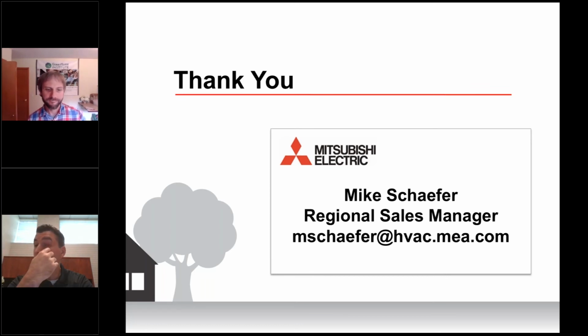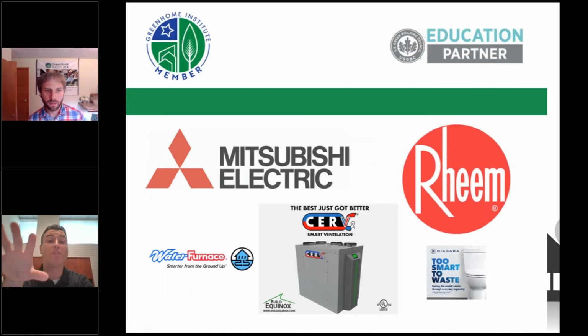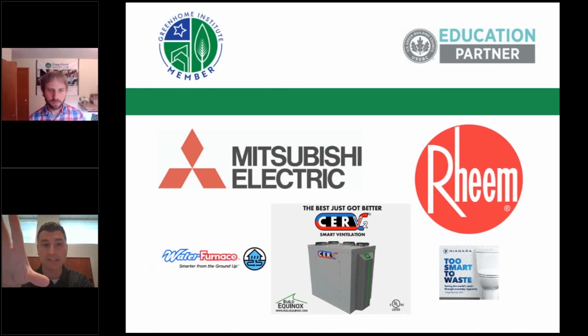There really isn't a set answer, but a lot of it is going to do with keeping the fan on. That's a key in heating: constant fan, because that's going to help with stratification of air. Moving that air around continuously, especially in heating, is definitely going to help with efficiency, because you're not going to have the compressor ramping up to heat the space and ramping down, up and down. Your highest efficiency is when you're cruising. So it depends on the application. If this home keeps the indoor unit operating at high fan speed, maybe that's because it keeps the controller, wherever you're sensing temperature from, satisfied longer, so you're not cycling on and off as much.